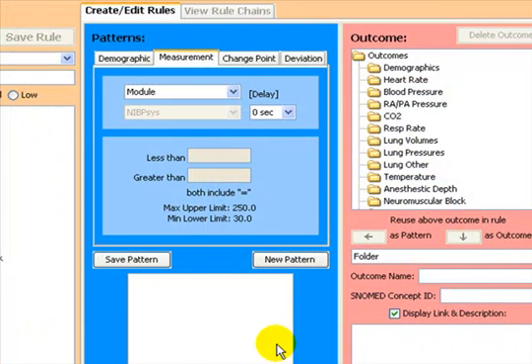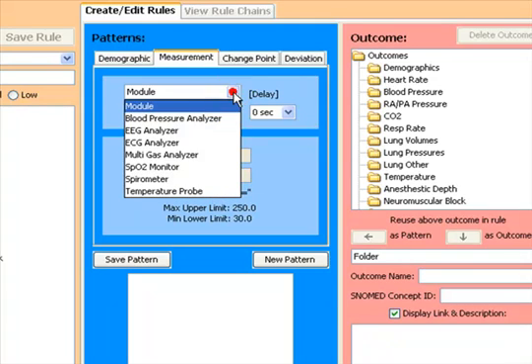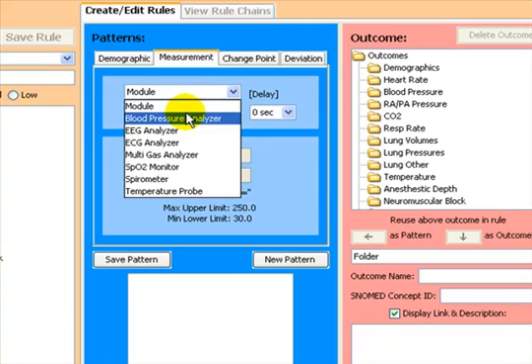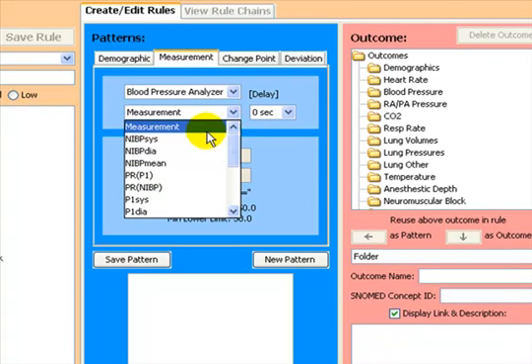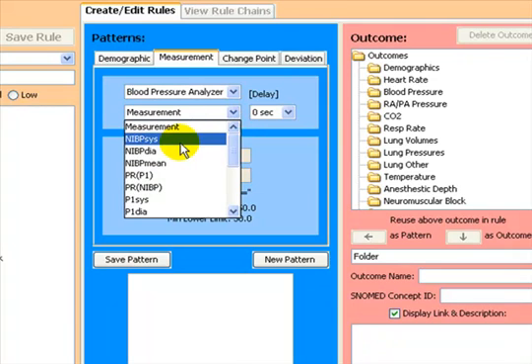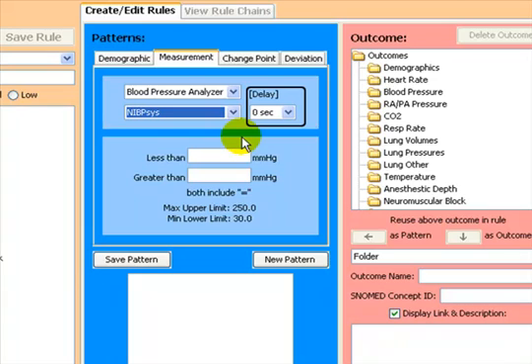Once we have selected appropriate rule name and folder, we can then select measurement patterns that will enable that rule to fire. We will select a measurement pattern from the blood pressure analyzer, which is a non-invasive blood pressure measuring device, and will select the systolic blood pressure recorded by that device. It is possible to introduce a delay at this stage that will reduce the number of false positive results.